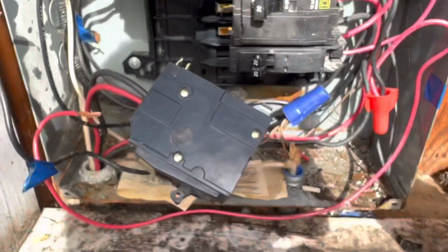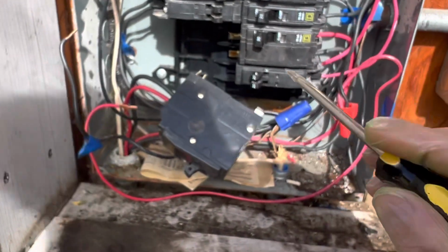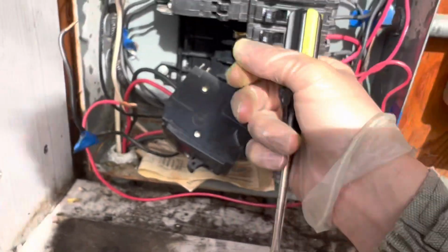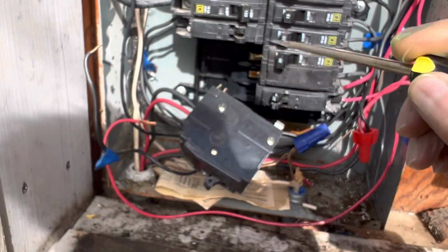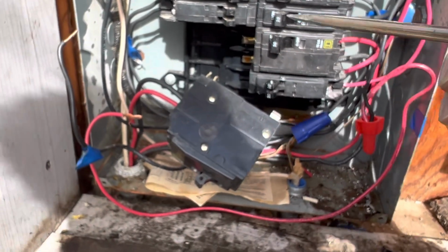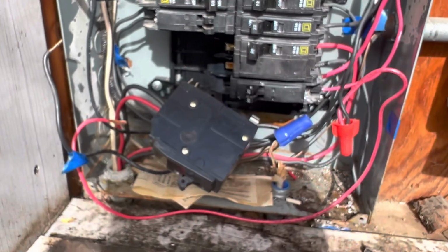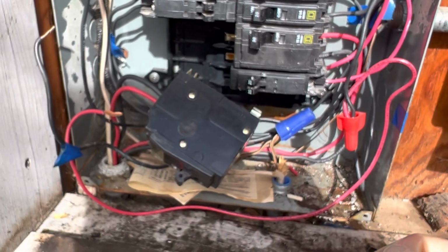In one of those, there was some burning, and on the back of the tab, inside right there where you see the touching face, where the blade goes down over, it was burnt. That was the burning, the ozone smell that was happening at that time. But then everything was re-pushed in and moved around, so it rubbed off the burn and made contact again, and it worked -- no lights flickered, the breaker, nothing burnt or anything like that.